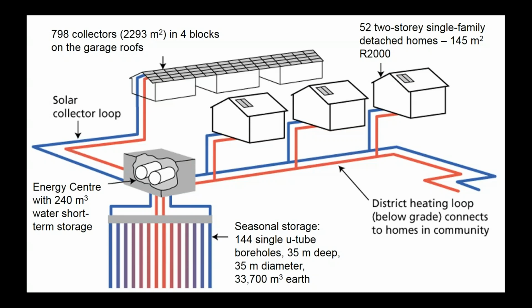The central system for Drake Landing does not supply domestic hot water. Domestic hot water is separate and individual for each house, with a solar collector system preheating the water for a gas water heater. So we don't have heat pumps. This system was designed as an ultra-low-temperature district heating system. Most of the time it supplies heat to the houses at 37 degrees and returns at about 28, which is quite different from most of what we've seen today.